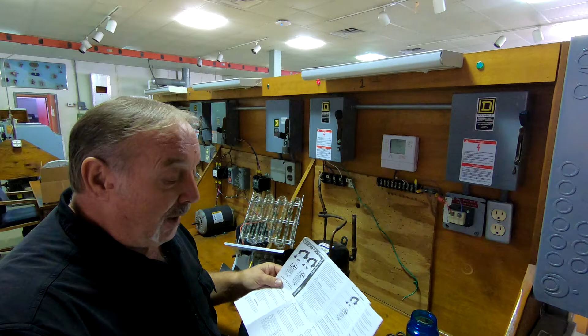Gentlemen, ladies, they make the manual so that you can figure out what each and every part of your meter can do, what the limitations of the equipment are, and also what the ranges are. It's important to note, and it says all over the front of your meter, not to exceed 600 volts, because that's the critical voltage level that the insulation, that's your probes and the insulative effect of the meter, can handle: up to 600 volts, no more.